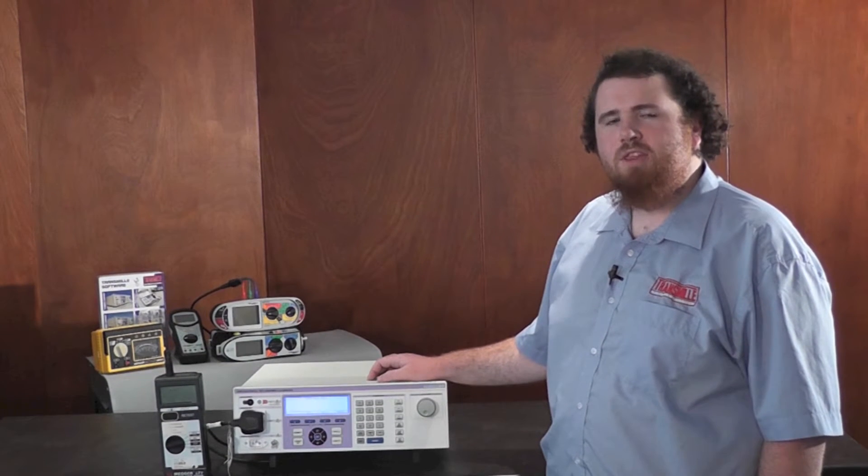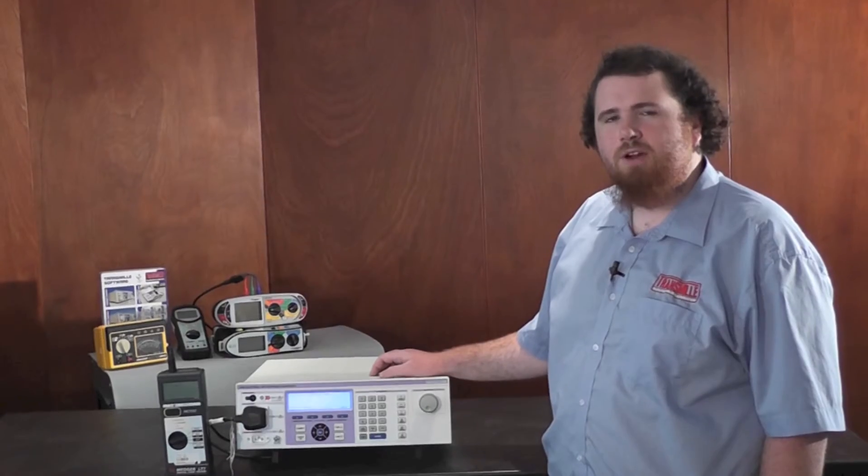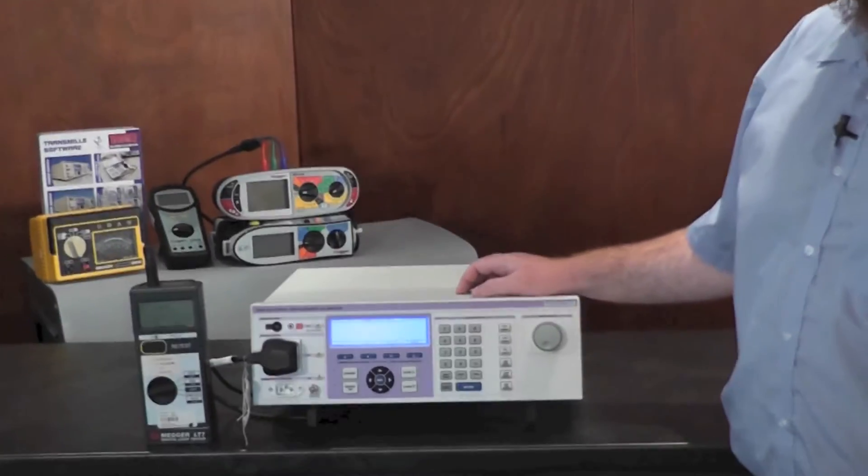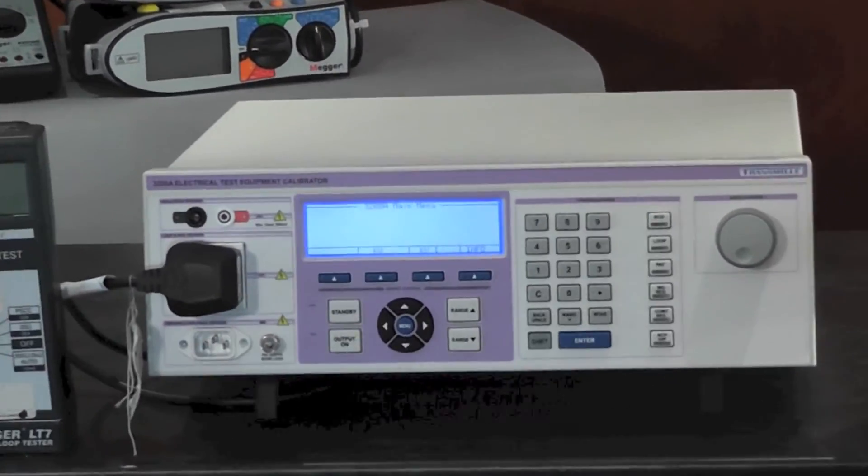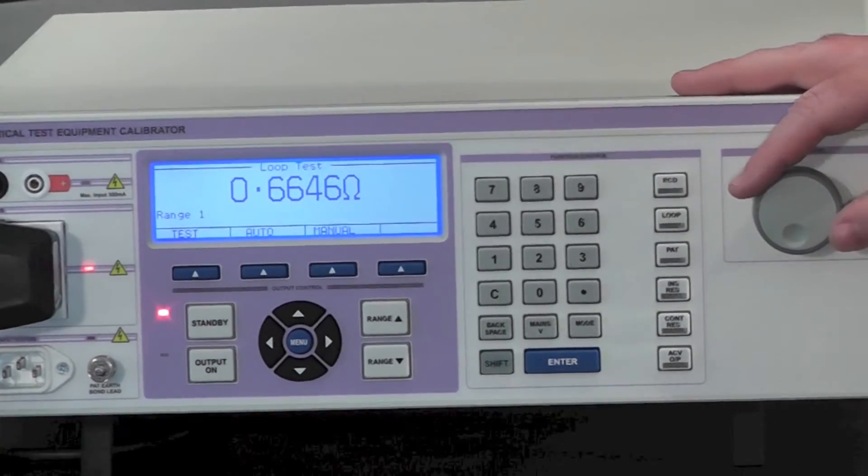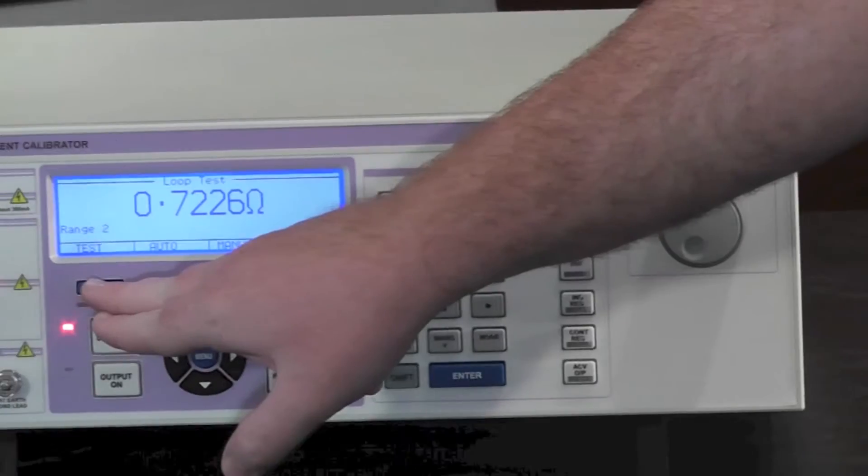Calibrating a loop tester with the 3200A is easy, especially with the auto loop function that automatically adds the loop resistance to the value indicated on the 3200. To test a loop tester, press the loop key, select the range using the digital control and press test.